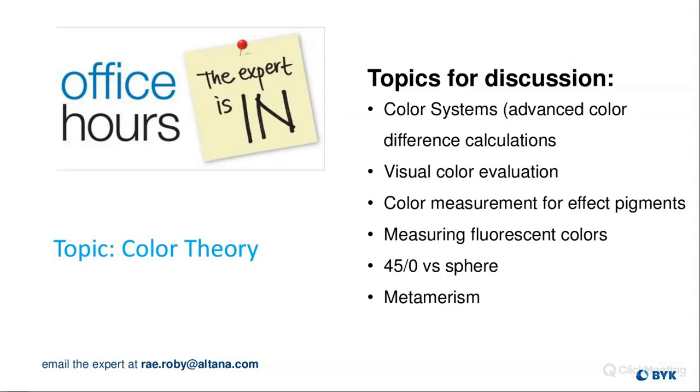Our next question, what's more recommended to use, LAB or LCH? And I think you answered that by steering us towards the LAB to avoid that manual work. Well, so LAB or LCH can both be done manually because it's all the CIE system. It just depends on if you have a chromatic color or a non-chromatic color. So LAB is usually used for colors that are under a chroma of 10, and anything over that you should use LCH.